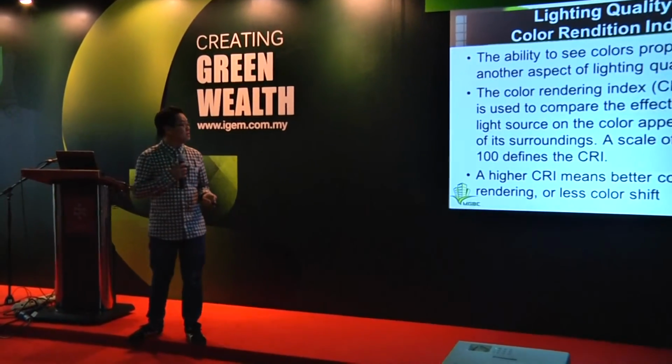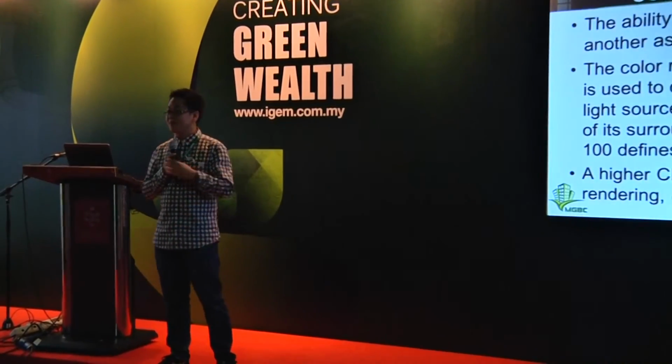Now, remember earlier we were telling you about color rendering index. Why street lights, low pressure sodium lamps, are very high efficiency but not used. High pressure sodium lamp is also high efficiency but people are changing to LED and things like that. Now, what color rendering is, basically, is when you have an artificial light source illuminating an object. The question is how vibrant the color is, how true the color is going to be reflected back to you. Now you think of it, under a street light, everything is yellow.